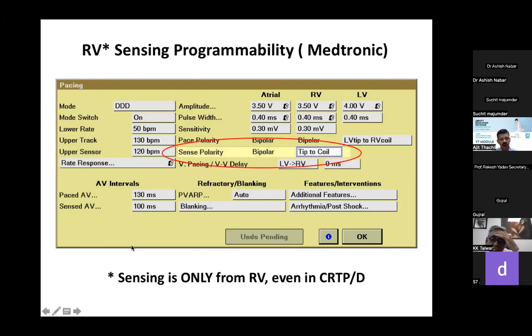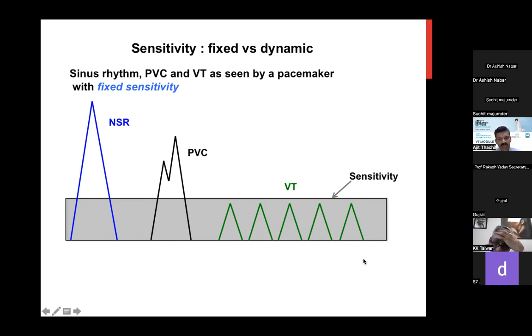The other part we need to understand about sensitivity is how it works. In an older generation pacemaker, any number below a particular value will not be sensed, and any number above it will be sensed. Look at this schematic where a sinus rhythm may have a larger amplitude, a PVC a smaller amplitude, and a VT an even smaller amplitude, in which case the ventricular tachycardia will not be sensed. Why does this happen? Mostly because of vector orientation, not because of the absolute R wave at that point.